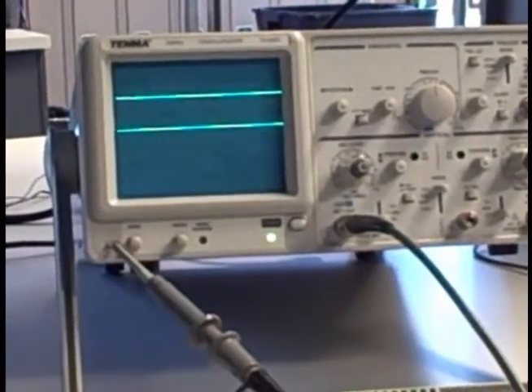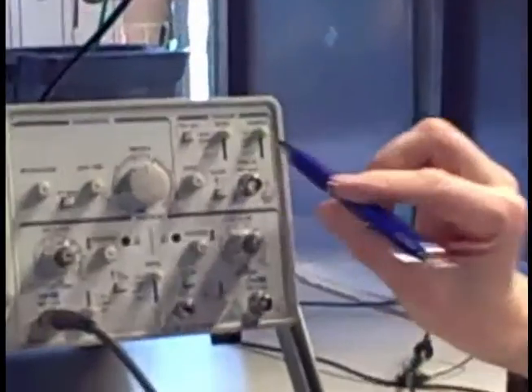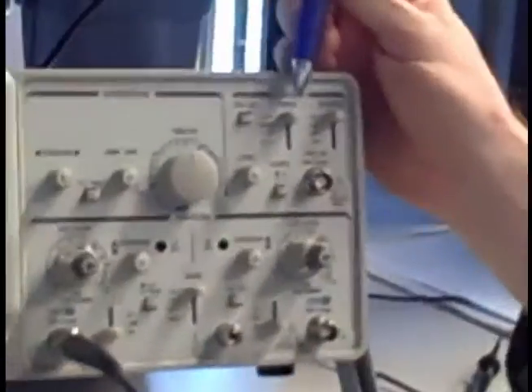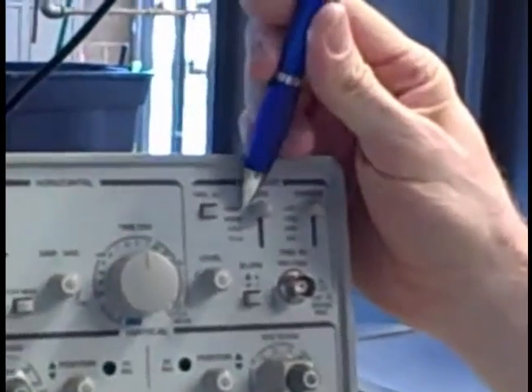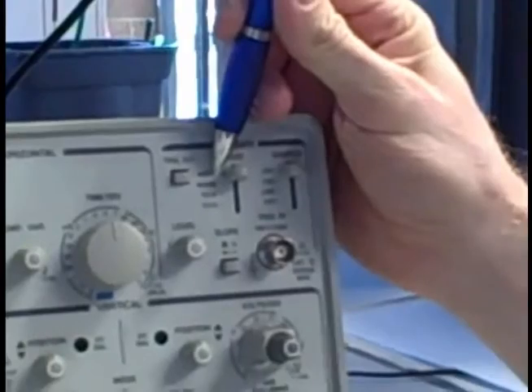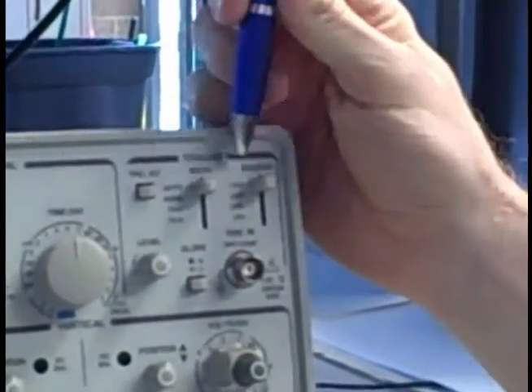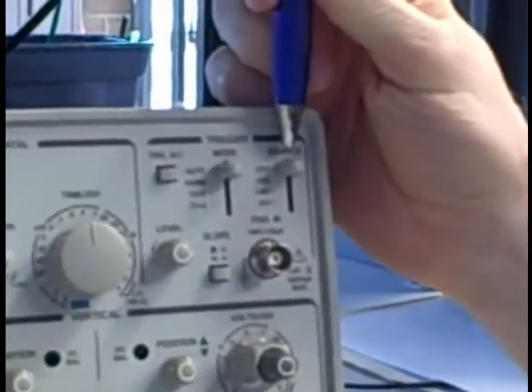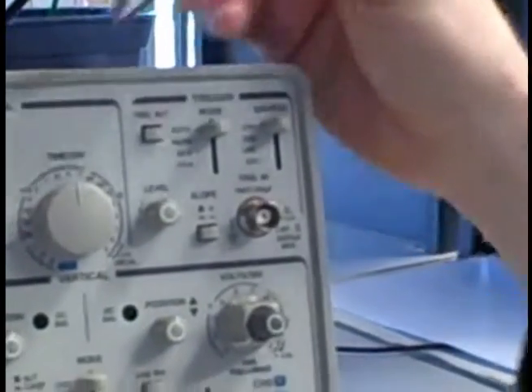So to lock this thing in, we have to focus into trigger mode. Lots of controls up here. First, the mode switch. I'll keep it in auto for now. That's the most useful mode for general purpose work. The source switch. Where do we get the triggering signal? Right now it's on channel 1, which stands to reason because our signal is coming in on channel 1.